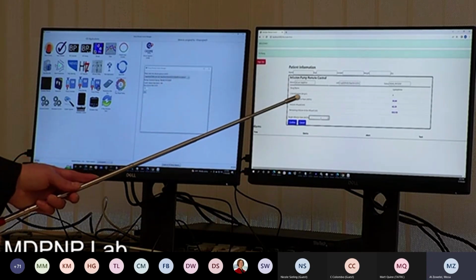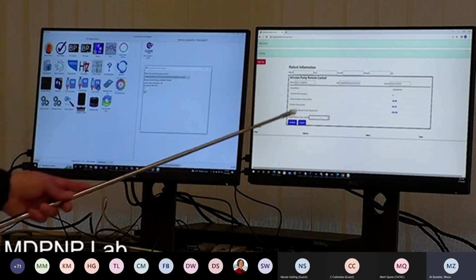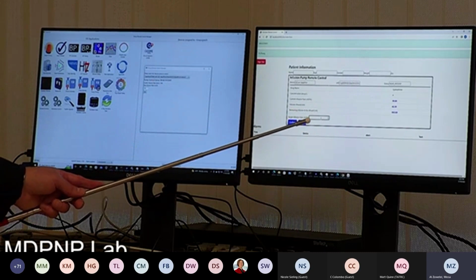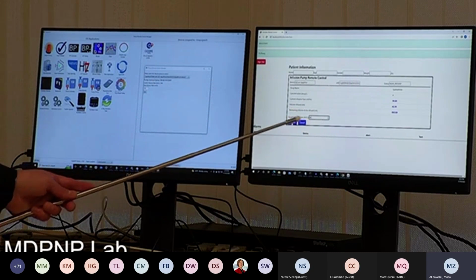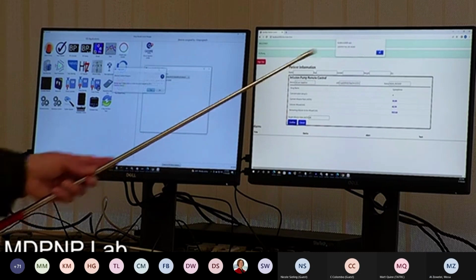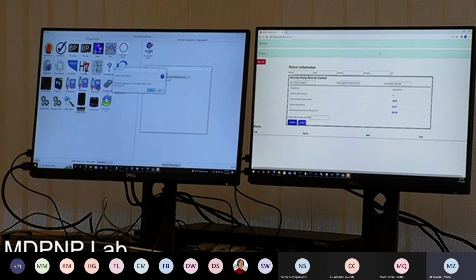On the remote, we're able to see the pump settings, and we're also able to type in a new rate there. So here we'll type in a rate of 40, confirm, and submit that request. Now, we could get ourselves into trouble here. If the bedside clinician really thinks it should run at 30 and the remote clinician really thinks it should run at 40, what prevents them from ping-ponging back and forth and adjusting that rate up and down, or changing the rate without the bedside clinician knowing what's going on?